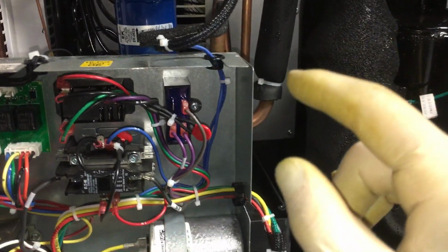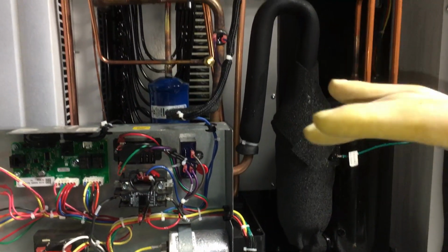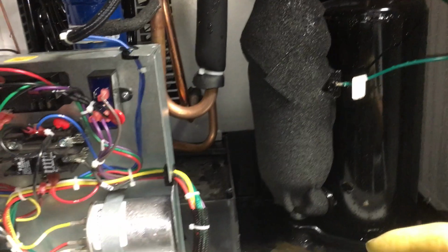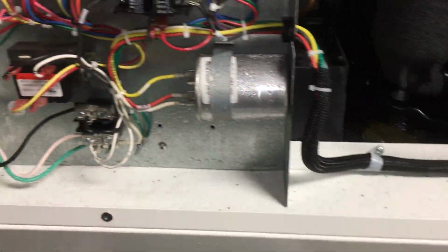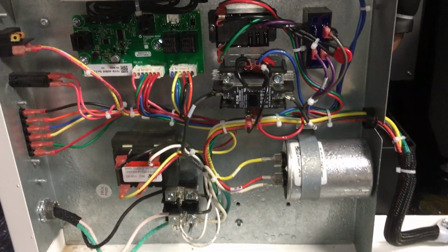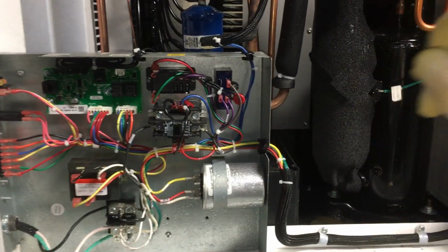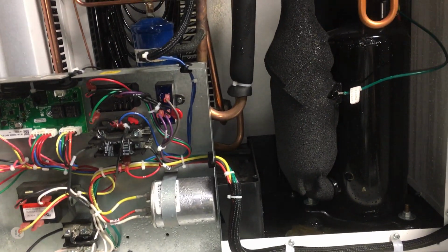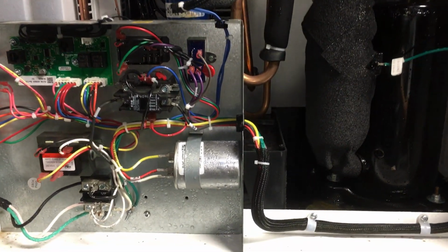There's the roof, but it's in an unconditioned warehouse where the inside basically becomes near the temperature of the outside. So in this situation, we had a massive amount of water accumulate. It poured out, it leaked through the roof downstairs, which I kind of knew what was going to happen. That's why I really told them these need to be mounted inside the room, but it couldn't.